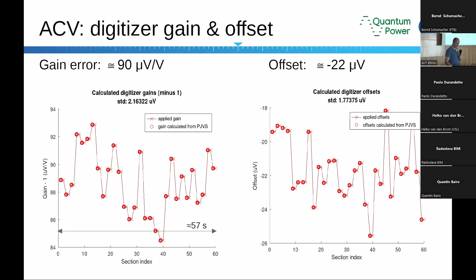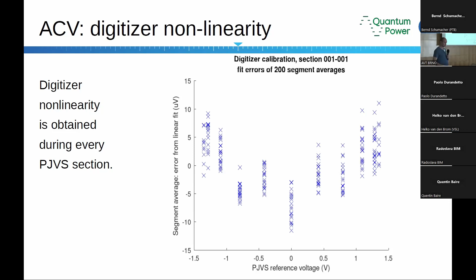And for example, during the data processing, I can also see the nonlinearity of the digitizer. You see that the digitizer got a few microvolts of nonlinearity. Maybe in next versions of the algorithm, I will try to do something with this nonlinearity, but it's future work. And this is the result that I got. The red and blue rectangles are the measurements using the differential method. So the classical Josephson differential method measurement is the amplitude of the calibrator, and on the y-axis you can see the difference from the nominal value, which was 0.8 volt RMS at 60 Hertz.